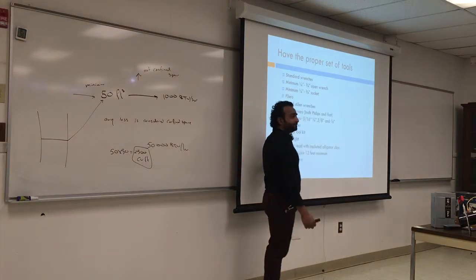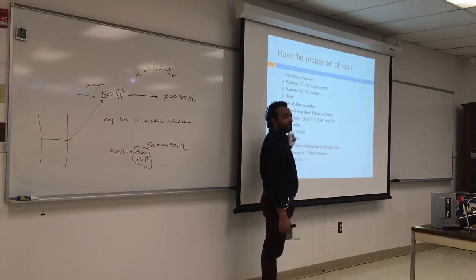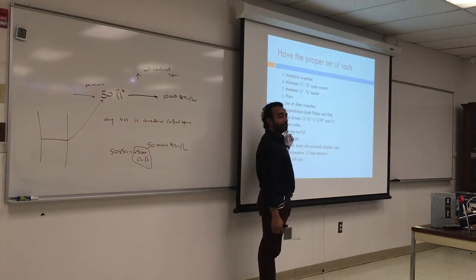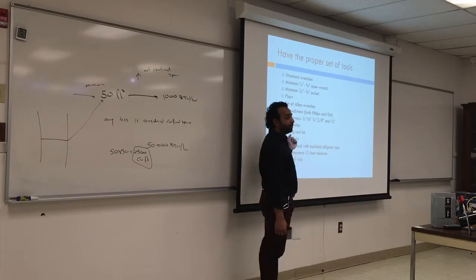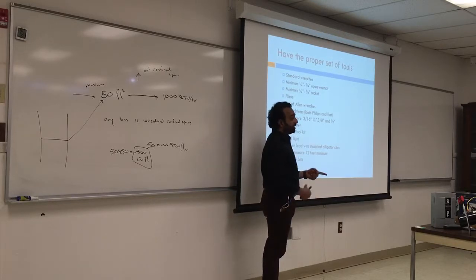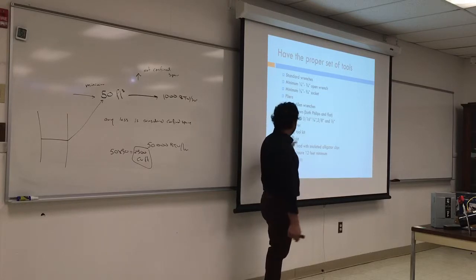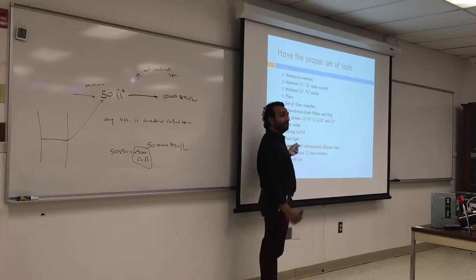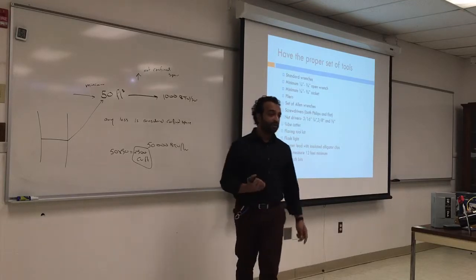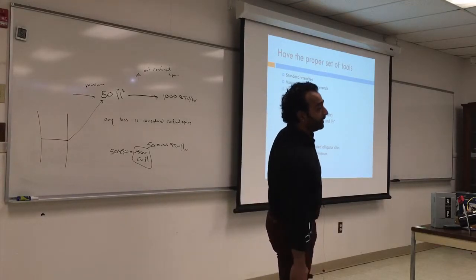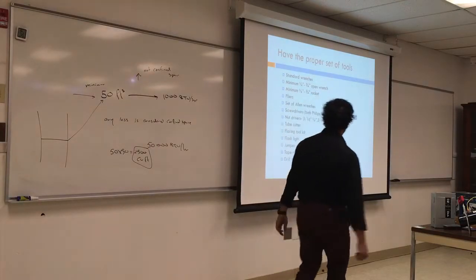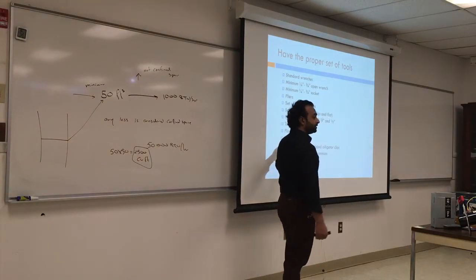Tube cutters, those for oil lines, in case you bent one of the tubes or it's leaky, you want to check it on the spot. Flaring toolkit, that's something you want to have with you the whole time. Again, any leaks, you can fix it on the spot. Have a flare joint and put them together, cut the pipe and replace it. Flashlight is very important to see inside the chamber. It's very dark in there, and also look at the heat exchanger to make sure it's clean. So flashlight is good. It's important.